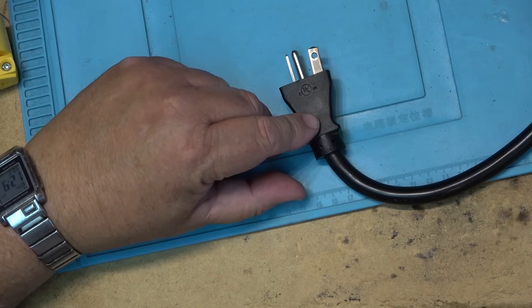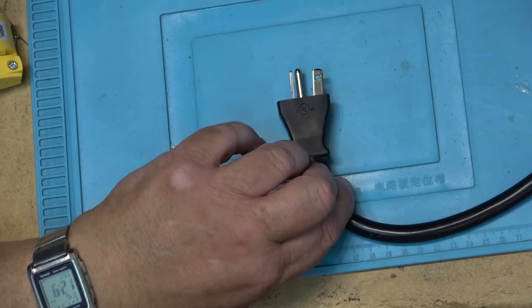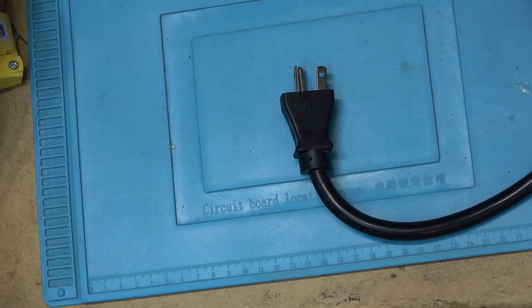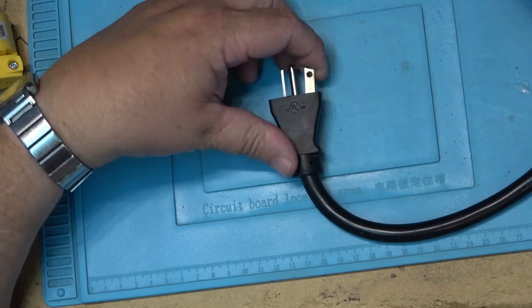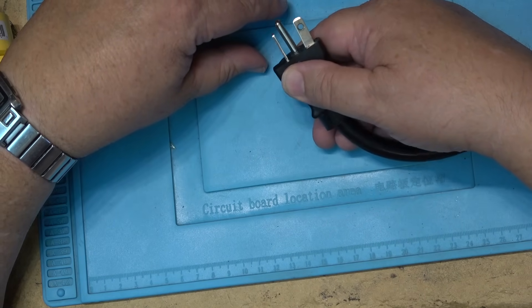My car charges at night when electricity rates drop — it comes on at 11 o'clock and takes a couple of hours. I happened to be walking through the garage and I do this once in a while: I run my hand down the electrical panel just to make sure nothing's warm, especially when things like the air conditioning are running. I checked the EV plug and touched it — it was warm, no, it was hot, really hot, unusually hot.